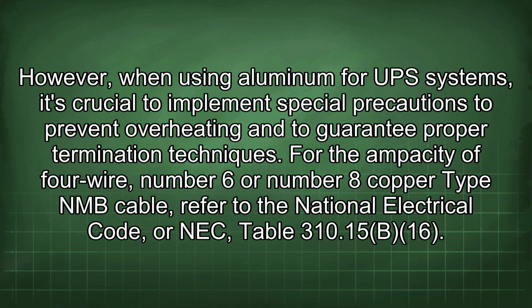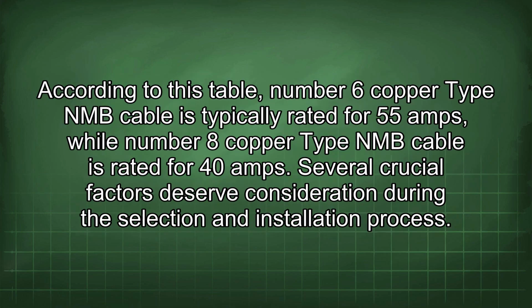For the ampacity of 4-wire, number 6 or number 8 copper type NMB cable, refer to the National Electrical Code, or NEC, Table 310.15(B)(16). According to this table, number 6 copper type NMB cable is typically rated for 55 amps, while number 8 copper type NMB cable is rated for 40 amps.